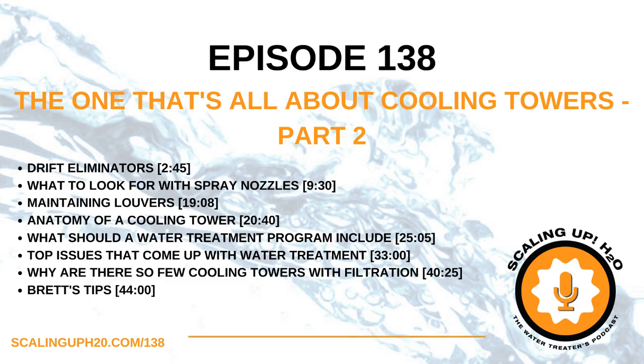All evaporative units should have PVC drift eliminators, typically. Think of the tower fill, the PVC fill that water's flowing down through. Above that, you'll also have a layer of PVC called drift eliminators. All it's doing is making about 3 different turns in that PVC, so when the saturated air, after it comes in contact with the water, flows up through the tower, it goes through those 3 passes of the drift eliminator, and any moisture caught in that airstream stays behind in the tower.